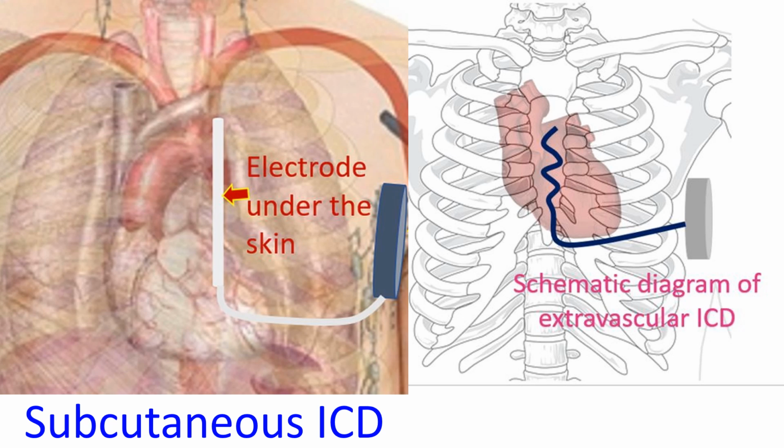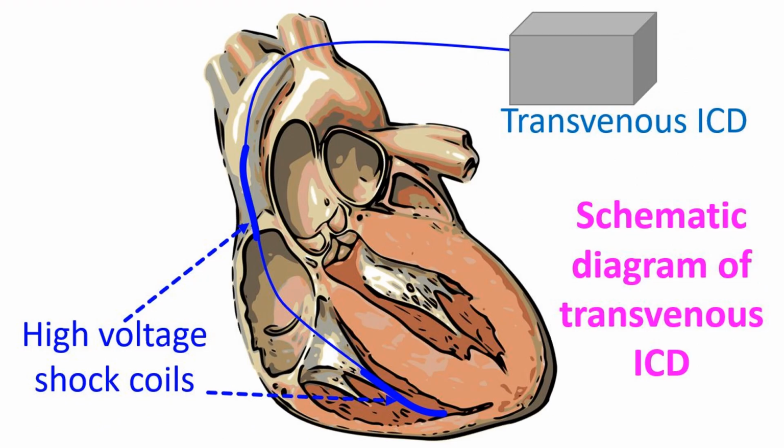conventional ICD system. Intravascular leads can get infected, fractured, or dislodged and occasionally perforate the cardiac chambers. Leads can also lead to formation of intravascular thrombi and cause thromboembolisms sometimes or venous obstruction. For these reasons, lead has been called as the Achilles heel of most cardiac implantable electronic devices, which include pacemakers and ICDs.